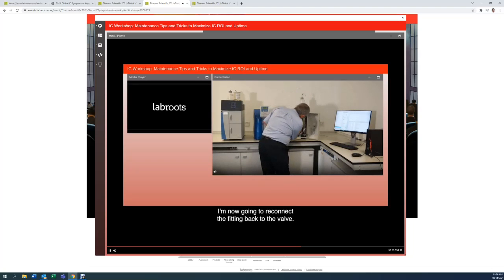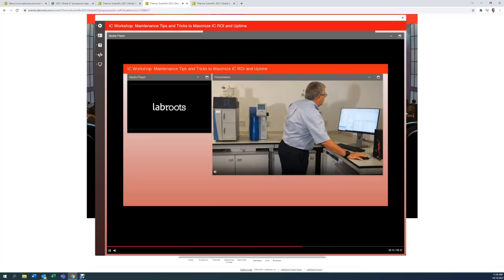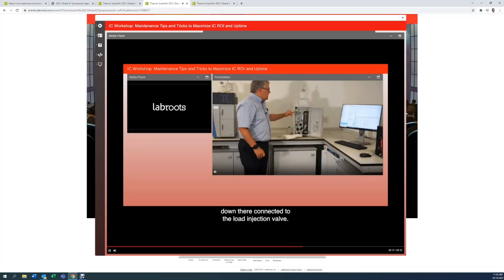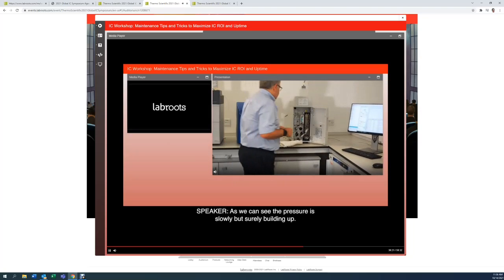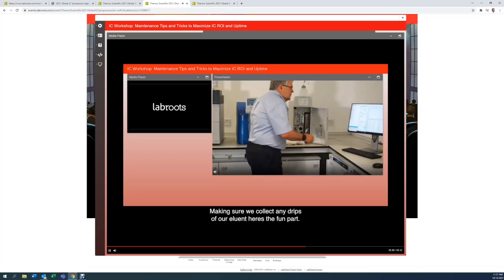I'm now going to reconnect the fitting back to the valve. We're going to talk about fittings later on in this presentation and how best to use them and how best to treat them. I'm now going to undo the fitting coming out of the valve to the column set and switch the pump back on again. This is going to test the back pressure of the pulse dampener connected to the load injection valve. And we can see the pressure slowly but surely building up. The load injection valve should give us absolutely no back pressure, or very, very little, maybe 1, maybe 2 psi at most. And as you can see, nothing.